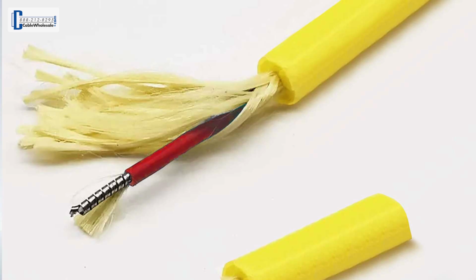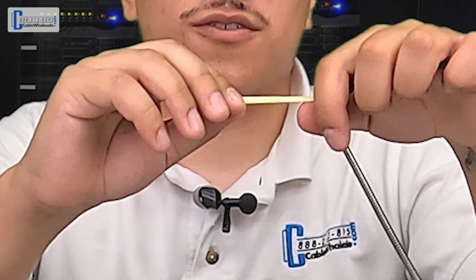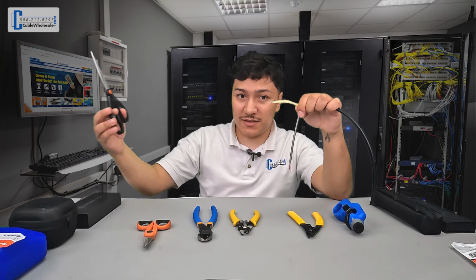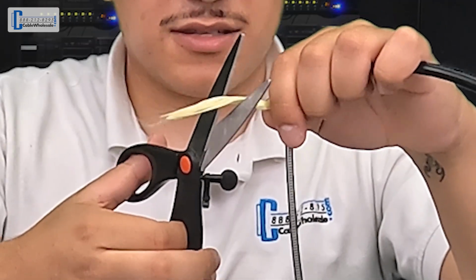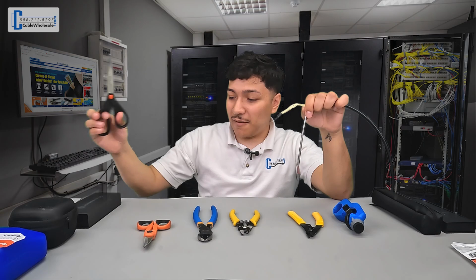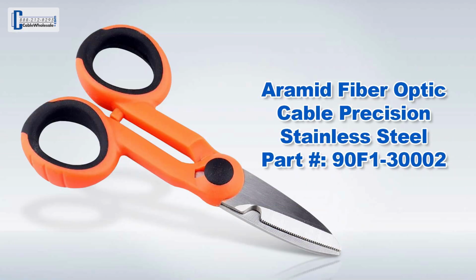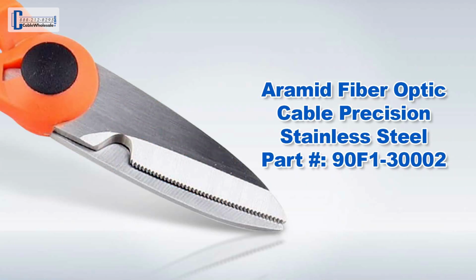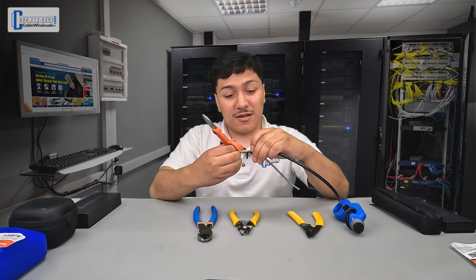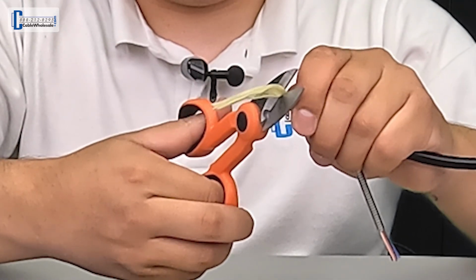Once the outer jacket has been removed from a bulk fiber optic cable, you'll typically find an aramid yarn or a Kevlar strength member. If it has to be cut, you can try using a regular pair of office scissors, but you're going to have a really hard time. It's not going to cut easily. So we have a special pair of fiber scissors that have micro serrated blades, which have small teeth machined onto the blade that bite and hold onto the strands of the aramid yarn for a nice and smooth cut. So it seems like a silly necessity, but trying to cut aramid yarn with regular scissors or even a blade is going to add a lot of time to your install, and it'll drive you slightly mad.